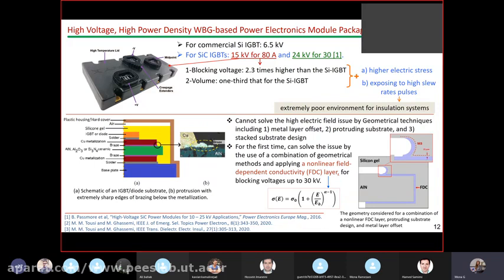Because of the high electric fields, especially at the edges of the copper metallization, partial discharges can be initiated from this region. The situation even gets worse because of the extremely sharp edges from the brazing below the metallization.